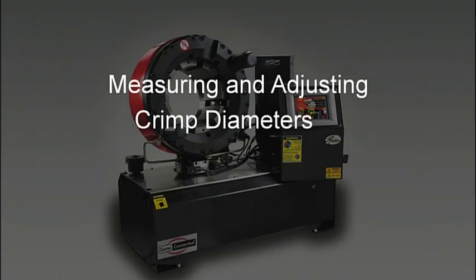Measuring and adjusting the crimp diameters. 1. Measure the crimp diameter. Measure halfway between ridges. To be sure the crimp diameter is being properly measured, mark a crimp flat. Beginning with that flat, count 4 flats to get the diameter. Be sure the caliper fingers do not touch the ridges or part number stamps. Measure halfway between the ends of the crimped portion of the ferrule.